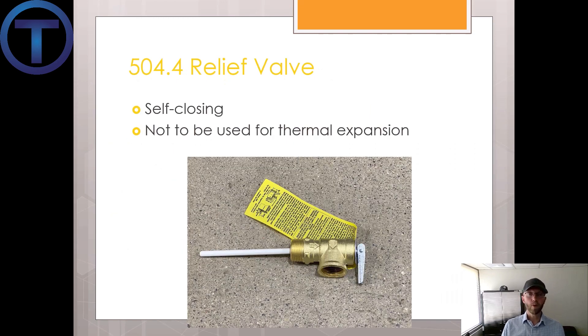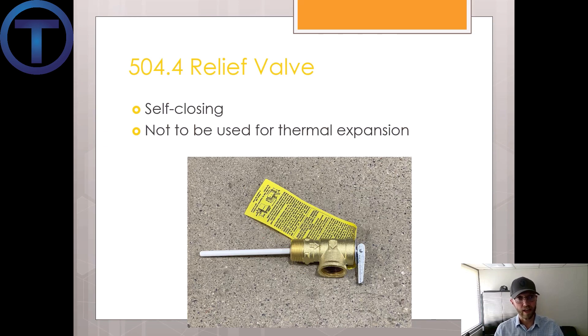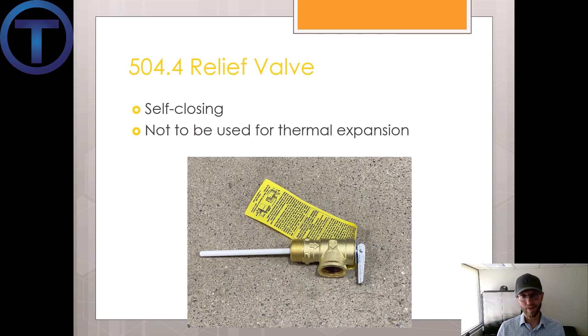504.4 talks about relief valves. These temperature pressure relief valves have to be self-closing and they are not to be used for thermal expansion. Thermal expansion is when hot water heats up and the molecules are trying to spread out. If you're containing those in a closed system, it just pushes the pressure up — that's why we have expansion tanks. However, some have thought that if you just let it go off the temperature pressure relief valve, it's still safe and not a big deal.